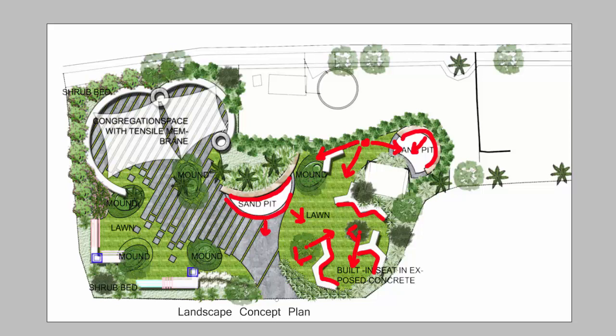the mound. And then for the pathwalk, what I'm planning to do is I will put bollard here because I need to make sure that I will have 20 lux on the pathwalk. So one bollard here, one bollard there. So maybe the spacing will be 3 to 4 meters away, and maybe one bollard here and also here. And if possible, I can also add some bollards here and also here. Okay, and what else do we have?